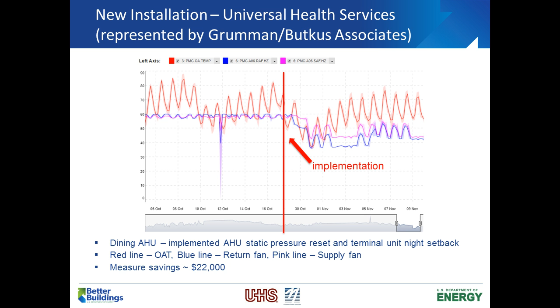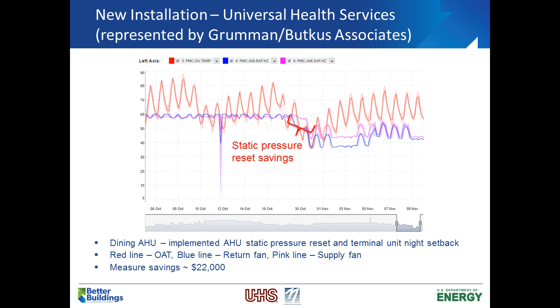So this is a measure that we actually implemented, and this is trend data that's pulling through on the Kaizen platform. It was for a dining room air handling unit. You can see left of that big bold red line was where the unit was running. The pink and the blue lines are the supply and return fans. They were running constantly throughout the day. And then after implementation, you see, next slide please. We actually did a static pressure reset, so that reduced the overall, what we consider our peak energy consumption. That's that drop. And then the next slide please.